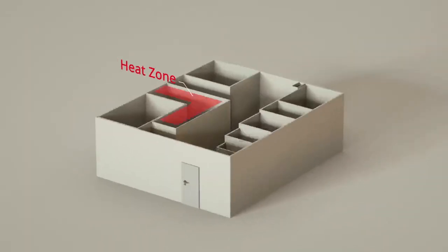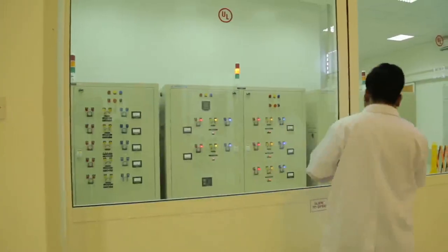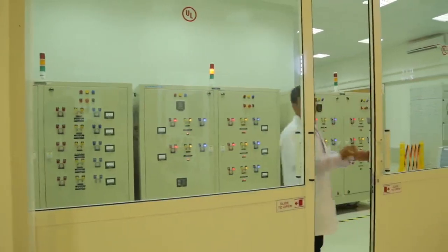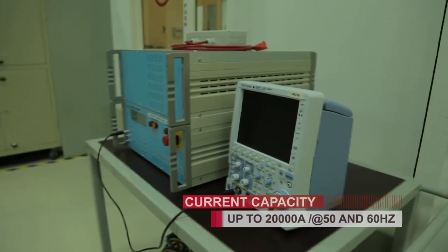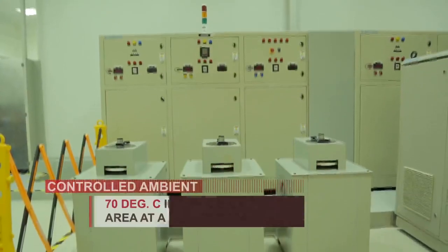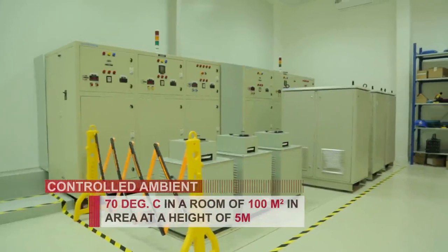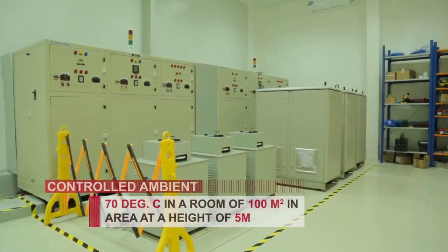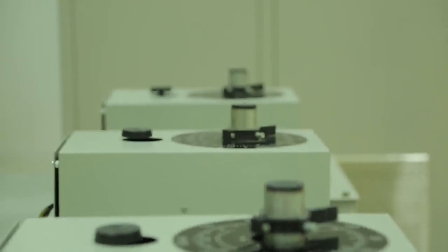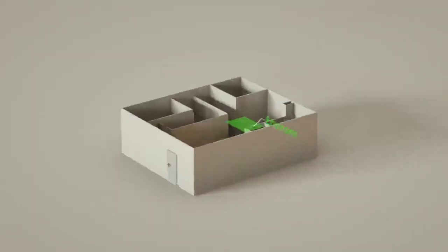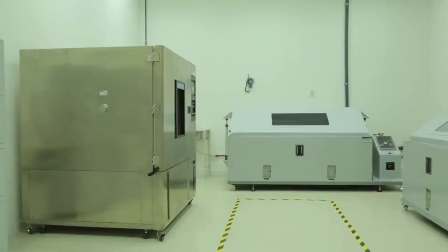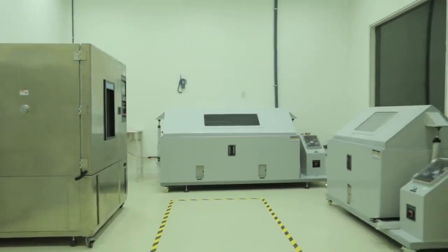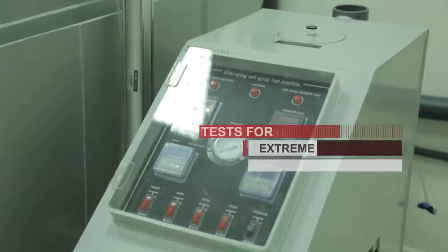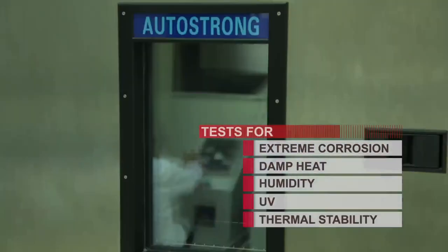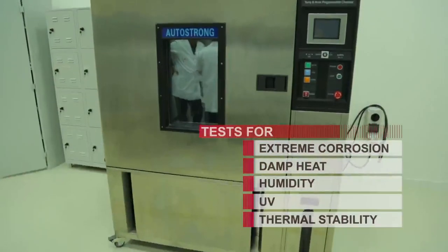The heat zone is the region's and one of the world's largest temperature rise test facilities, with current capacity up to 20,000 amperes at 50 and 60 hertz, and elevated controlled ambient of 70 degrees centigrade in a room of 100 square meters in area at a height of 5 meters. This is fully automated and remotely accessible. The environmental zone offers multiple mechanical tests for ordinary and hazardous location assemblies, and environmental tests for extreme corrosion, damp heat, humidity, UV, and thermal stability.